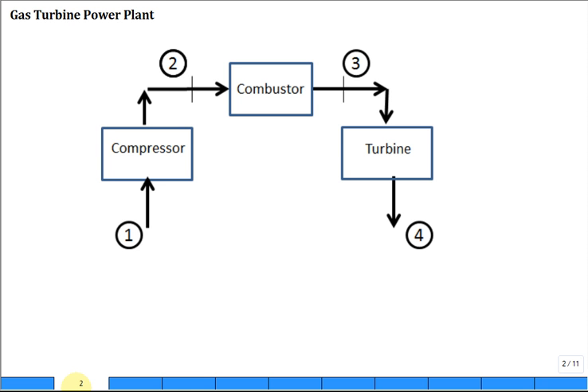So a gas turbine used in a stationary power plant has a compressor which takes and ingests outdoor air and it boosts the pressure. The pressure at 2 is a factor times the pressure at 1, greater than the pressure at 1. Often they specify the pressure ratio P2 divided by P1, maybe that's 9. The pressure after the compressor is nine times the inlet pressure P1, or maybe it's 10 or 11 or 12, but it's a pressure ratio.